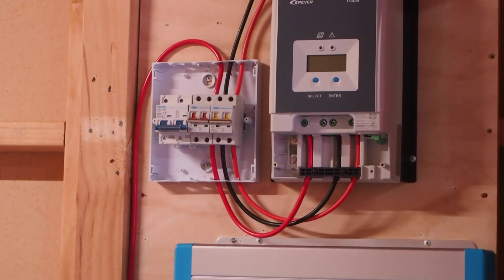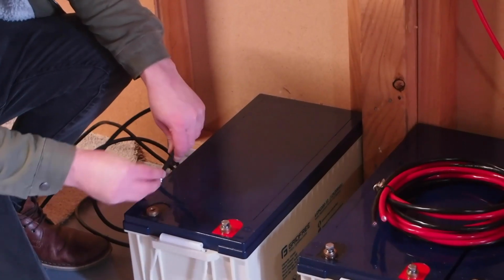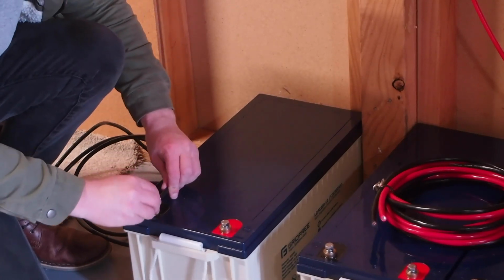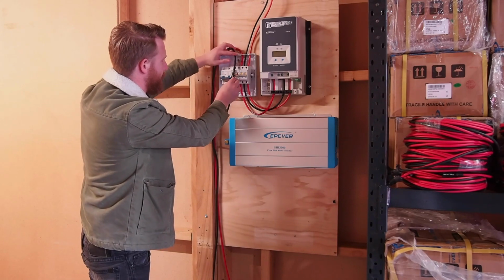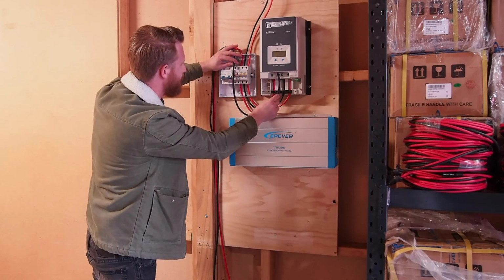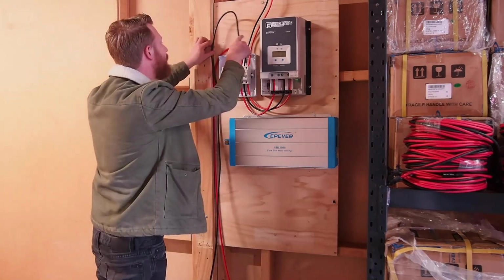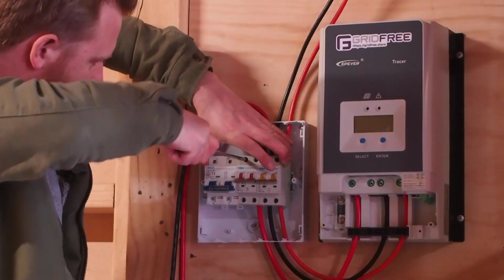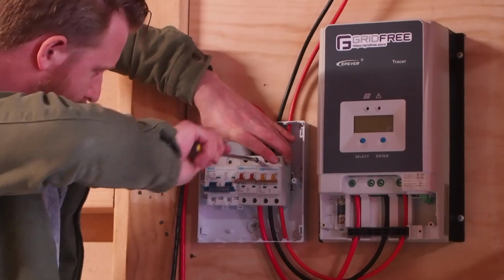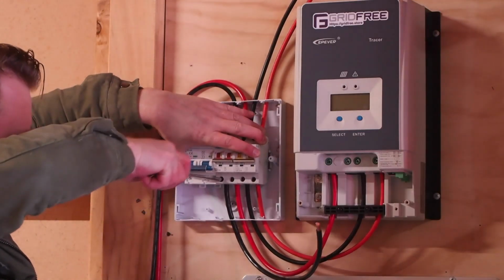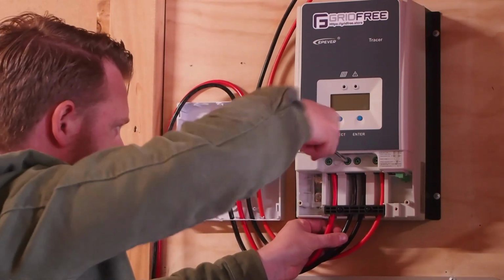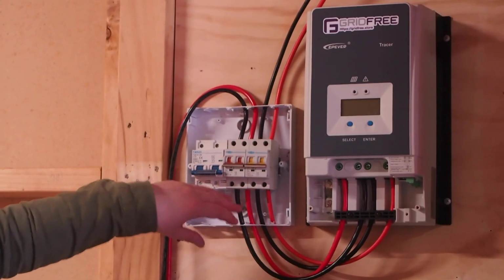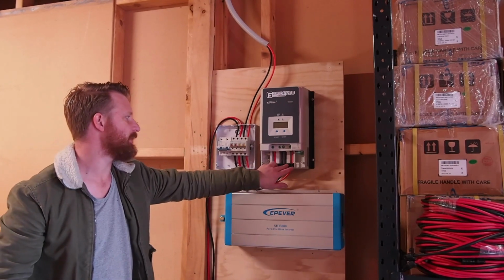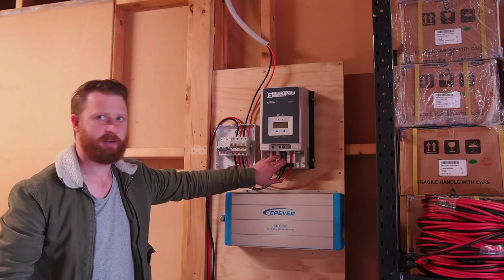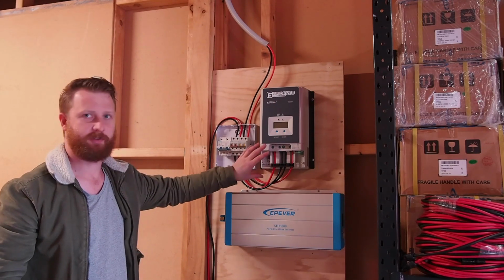We're just going to do the same thing for the negative. Taking our negative cable and attaching it to the negative of the battery on the other side of the battery bank. Again, making sure that we've still got enough to run to the charge controller. So now that we've got this last negative run finished, the wiring to this charge controller is complete. The last thing to do is tighten down these two screws here to clamp these cables down, just to give them some extra strain relief, and then we'll put the front case back on.